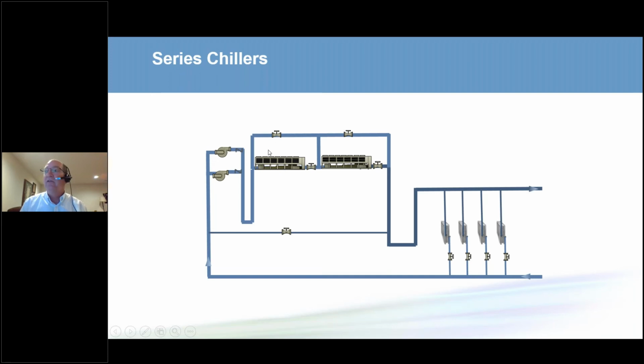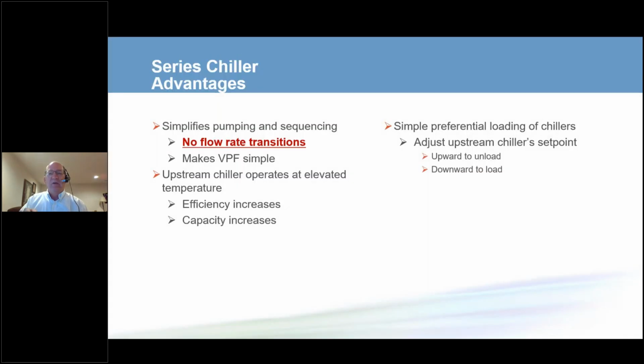This works better when we have a delta T of at least 8 degrees C. If we only have a delta T of 6 or 7 degrees C, the pressure drops will be too large, our pump power will be too large, and we will use more power in our system. But once we get to an 8 to 10 degrees C delta T and larger, we can reduce those pressure drops. Another thing that happens in the system is this upstream chiller operates at an elevated temperature. It isn't making the system supply water temperature. That chiller becomes more efficient, and that offsets any increase in pumping energy and pumping power. So this upstream chiller offsetting the pump power increase is wonderful.